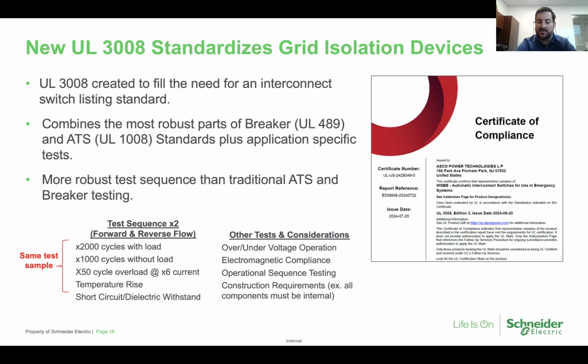And so all these things come together, right? So the National Electric Code is now allowing inverter-based sources for standby power applications. It's requiring that isolation be put in place to allow it to operate properly when there is the need for resiliency instead of the need for energy cost optimization. But if you are putting an isolation device in, it must be listed and labeled for the specific application of interconnection and isolation. And that's been answered by UL 3008, the new standard that these types of solutions can be listed to for applications such as Article 700 facilities and loads in a hospital, for example. And all that comes together.